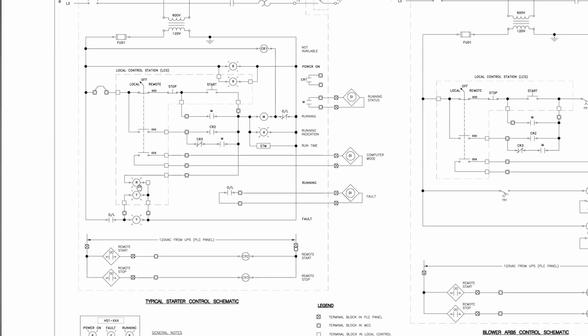Over here, we've got a red and a yellow light. So there's a fault light. Red is a running light and yellow is a fault light. So when looking at drawings, it's always good to look all the way across. You might have descriptions somewhere that may not make sense until you follow it to the other side.